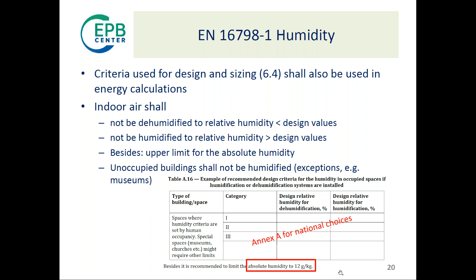You see here again a table, an Annex B table with filled-in values for the different categories. This can, of course, also be defined on a national basis, with one exception: the absolute humidity shall always be limited to 12 grams per kilogram. This is a limit which is not given free for national choice. It's mentioned in both Annex A and Annex B, and it's hardwired, if you wish.